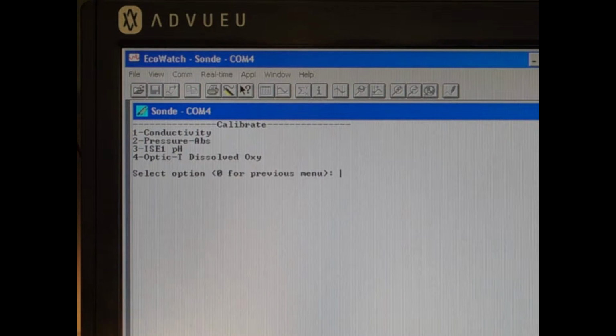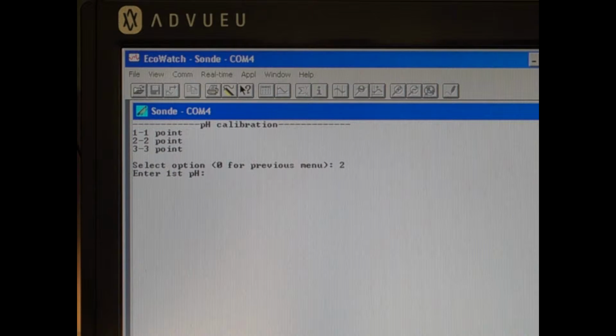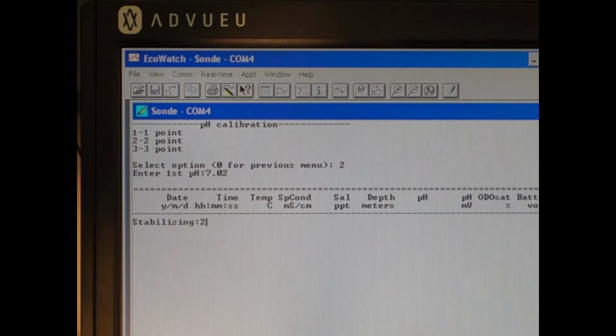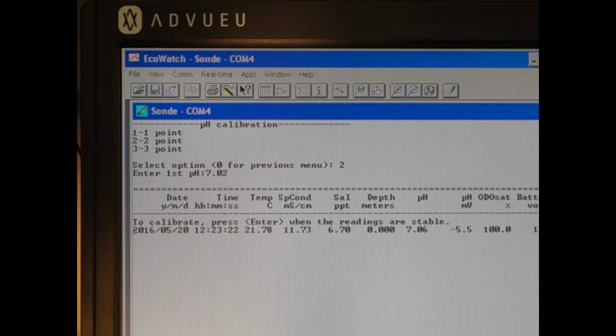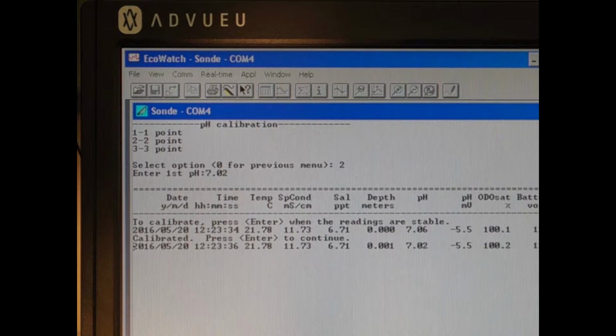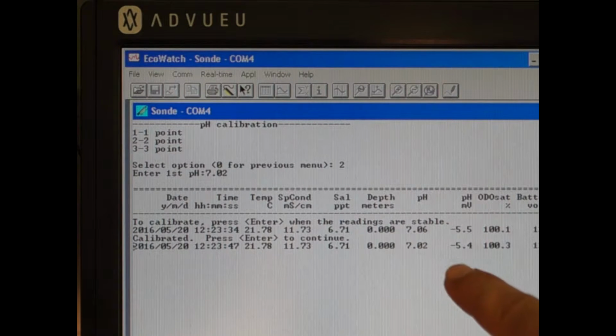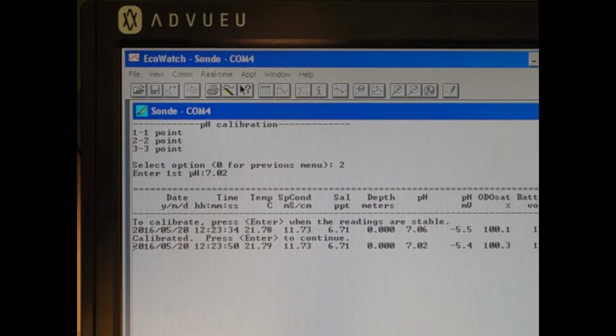So I hit 2 for calibrate and pH. We're going to need a 2-point calibration. Now the first pH, using the table that was on the box of the pH standard, is 7.02. Now the initial reading for pH is 7.06. You write that down on our calibration sheet. And we push enter. And it calibrated to 7.02. And we push enter again. And it calibrated to 7.02. Now we need to write down the pH millivolts. That's negative 5.4 on the calibration sheet. So we push enter. Now it's ready for the second pH value.